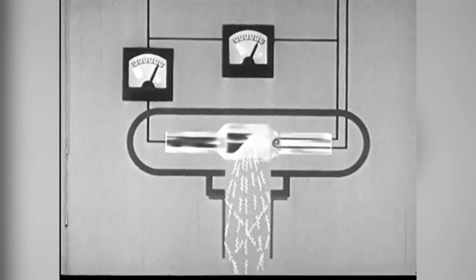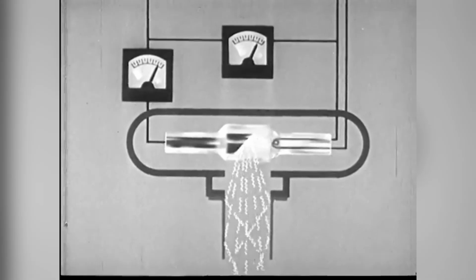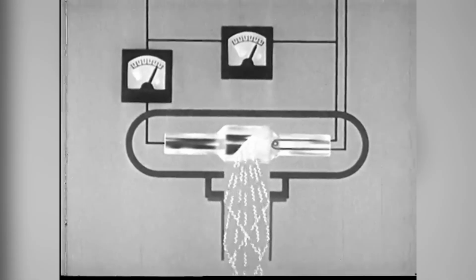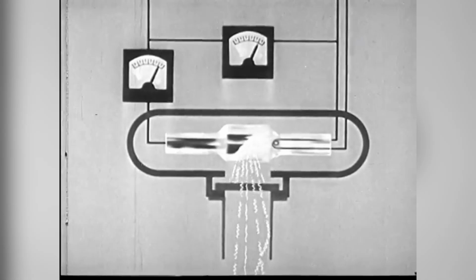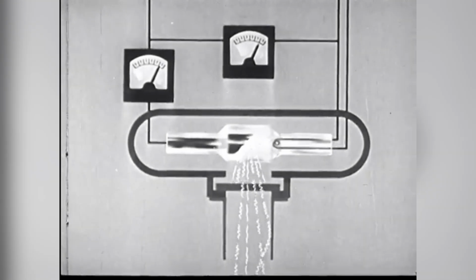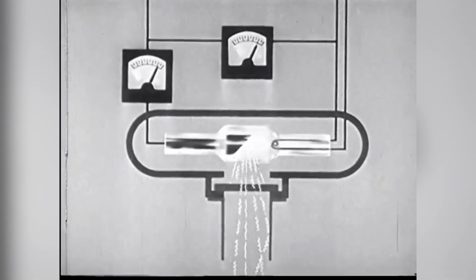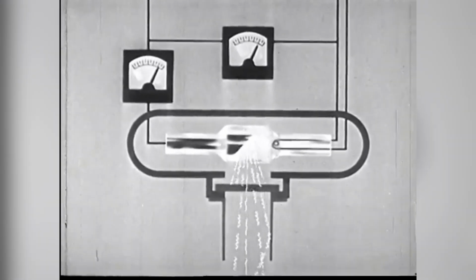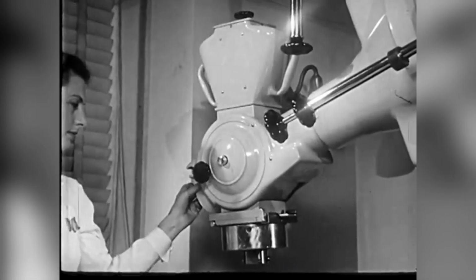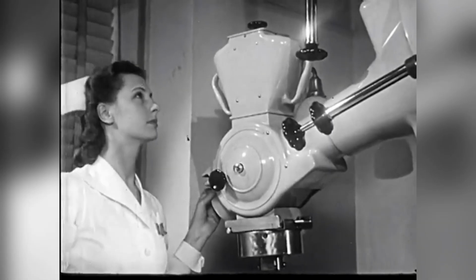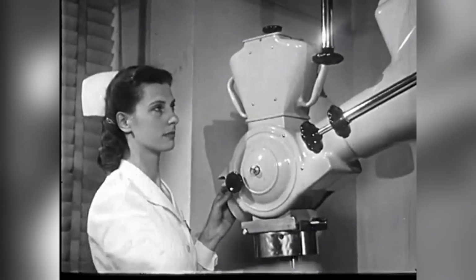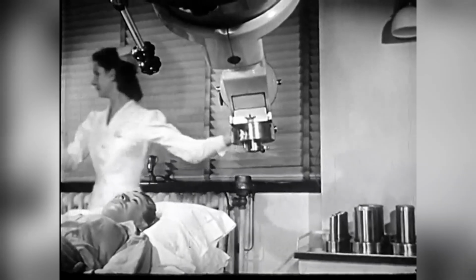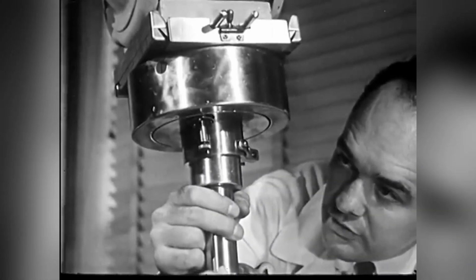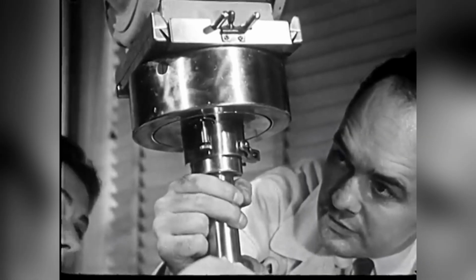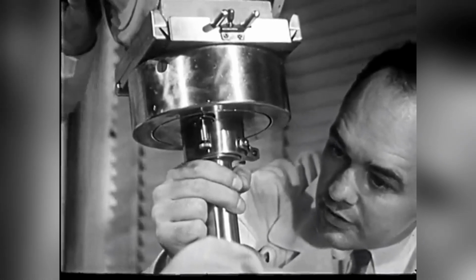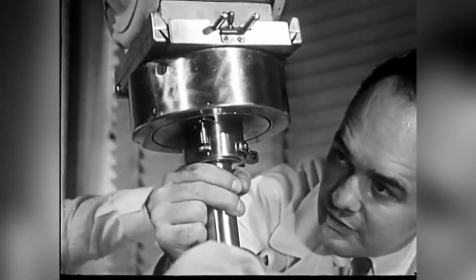A dual-mode accelerator does two completely different jobs along the same beamline, and the settings for one are lethal in the other. In electron mode, the beam is deliberately weak, and scanning magnets spread it out before it reaches the patient. Photon mode raises the beam current roughly 100 times, because the target and the beam flattener behind it, a very efficient attenuator shaped like an upside-down ice cream cone, absorb most of the energy before any of it reaches skin. Remove the target and the flattener from the path while the current is still set for X-ray work, and a patient receives the unattenuated beam.